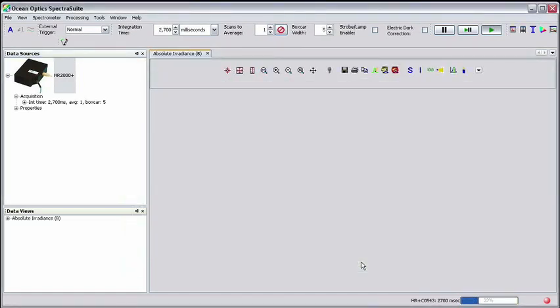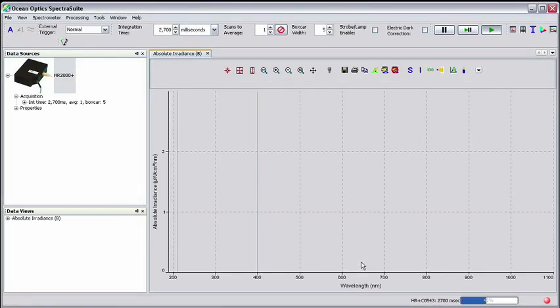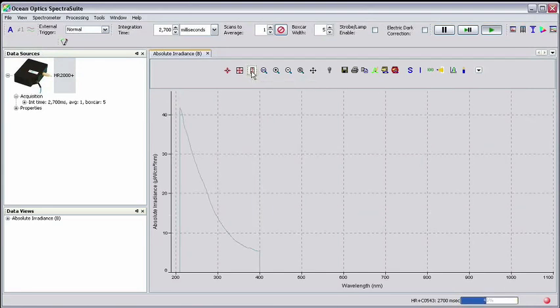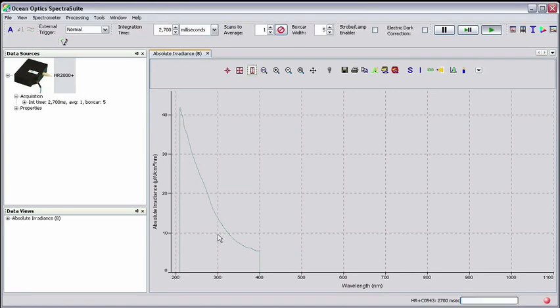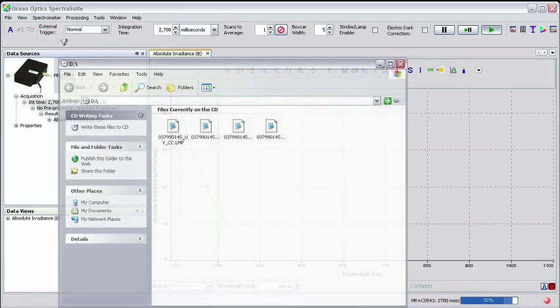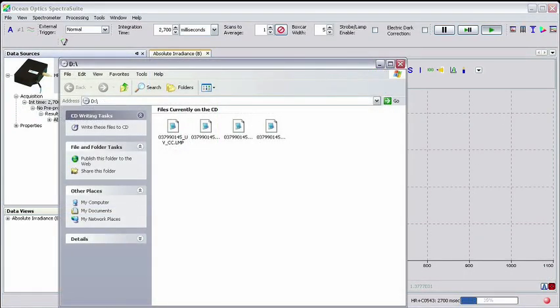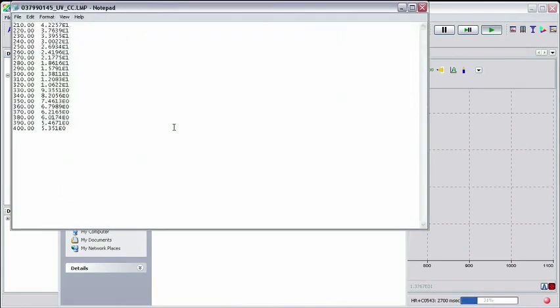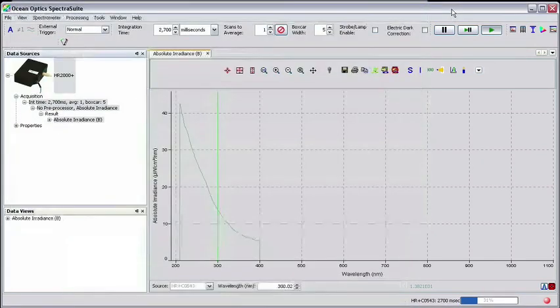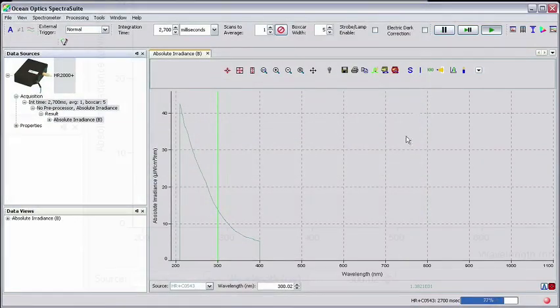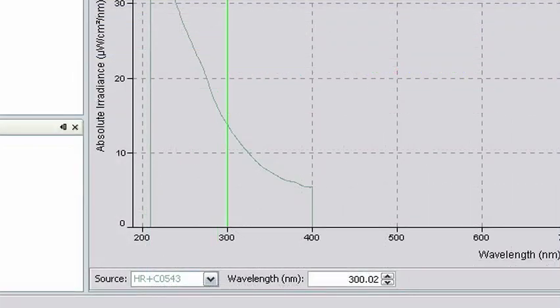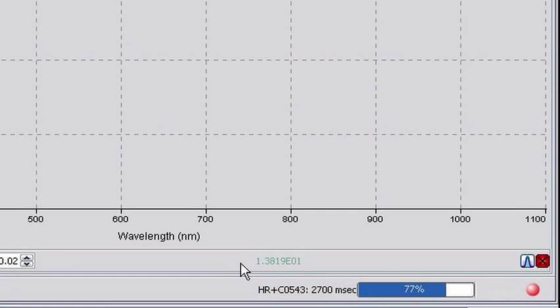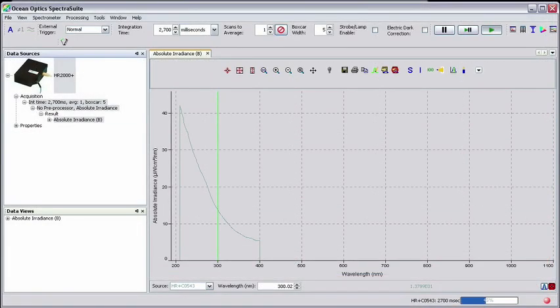In the main Spectra Suite window, you'll see a graph of the calibration light source. A good test to see if you've performed the calibration correctly is to cross-reference the values listed in the lamp file with the values being measured in Spectra Suite. For instance, our lamp file shows a value of 13.8 microwatts per centimeter squared per nanometer at 300 nanometers. Clicking on the spectrum graph at 300 nanometers to activate the cursor, we see that the value at 300 nanometers is approximately 13.7 microwatts per centimeter squared per nanometer. Therefore, it looks like we've done the UV calibration correctly.